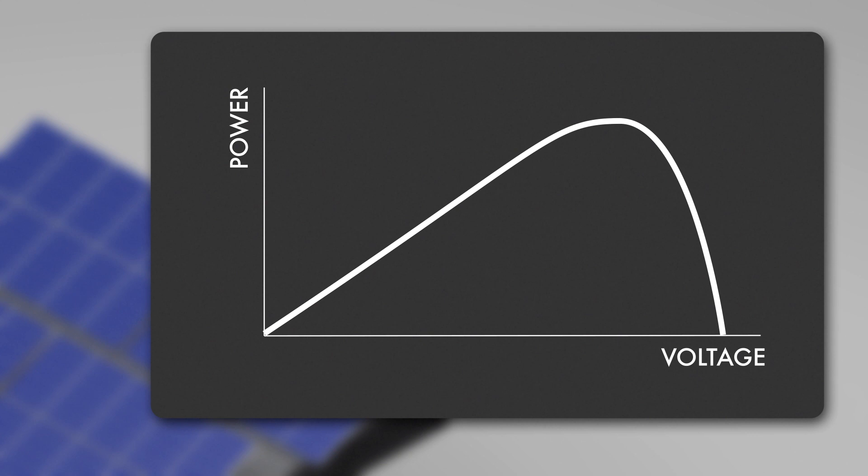There is an optimum operating point, detected by an MPP tracker within each solar inverter, extracting the maximum power of the PV array. This maximum point on the power curve is called maximum powerpoint, or MPP, and the correspondent voltage is called MPP voltage.